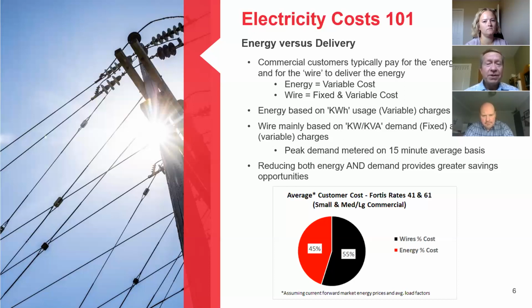So it's important to note that the peak demand is measured on a 15-minute average basis. A customer only needs to set a peak well above your normal operating demand for 15 minutes and your entire month of charges will be based on that peak demand that you set by operating at a higher level for only 15 minutes. And then additionally, most wires rates for small commercial and larger customers have what is called a ratchet. What that means is that the monthly peak demand that you set is typically billed on the higher of the actual peak that you set during the month, or a percentage, and in a lot of rates, that's 85% of the highest peak that you set in the past 12 months.